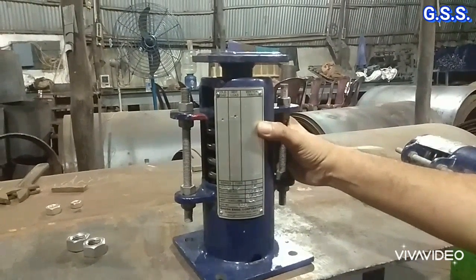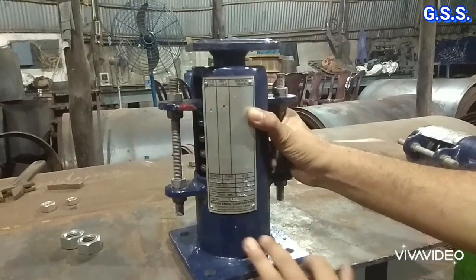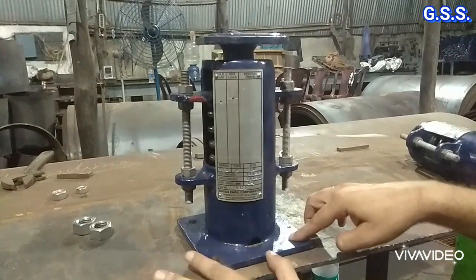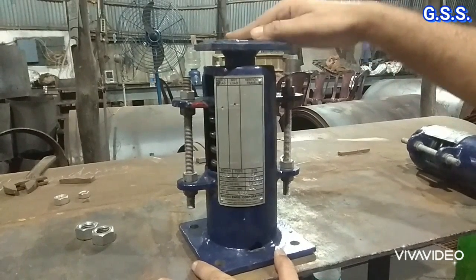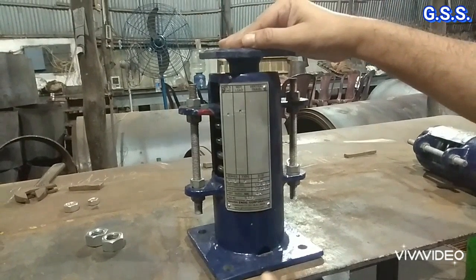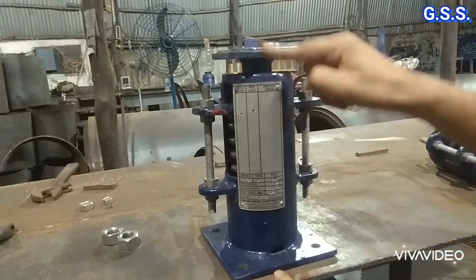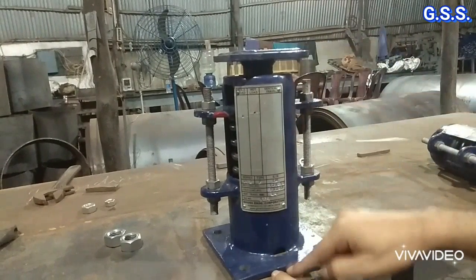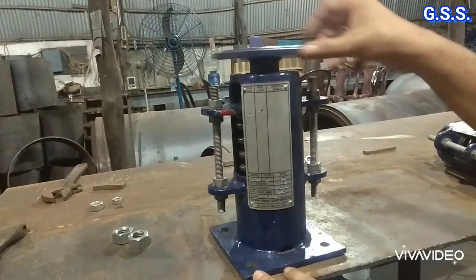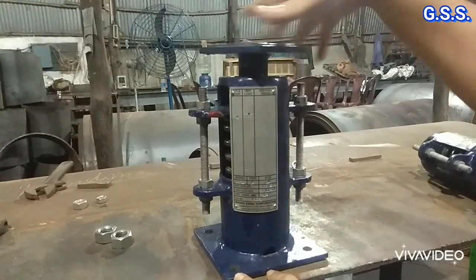This is a bottom spring support. This is the base plate, which can be welded over the structure or bolted through four bolt holes. This is a bottom-supported spring, meaning the pipe shoe will rest over this load flange. At site, we can adjust the height — suppose this height is 250 mm and the gap between structure top and pipe shoe bottom is 270 mm. If we rotate this load flange, there is a height adjustment provision of around 40 to 50 millimeters.